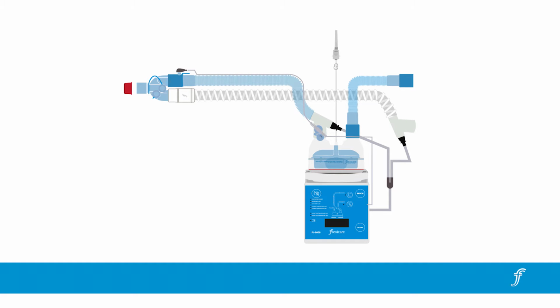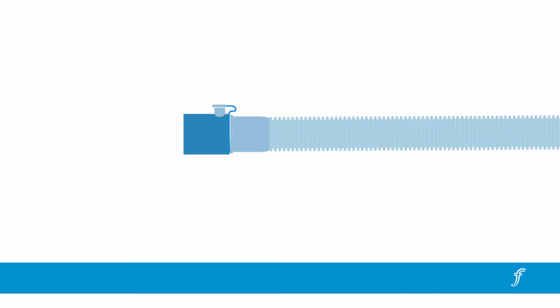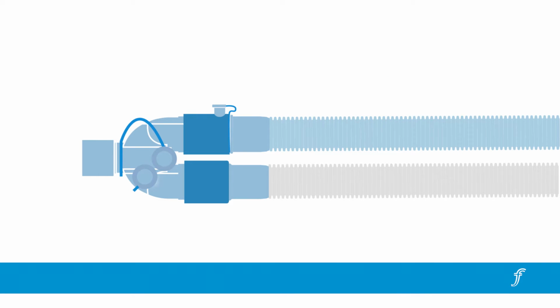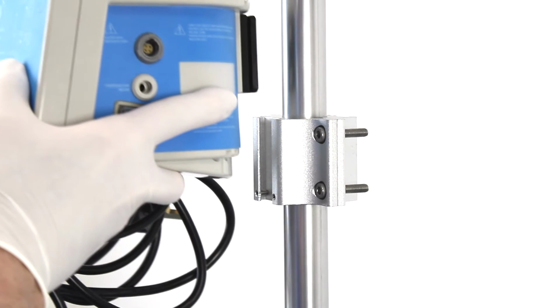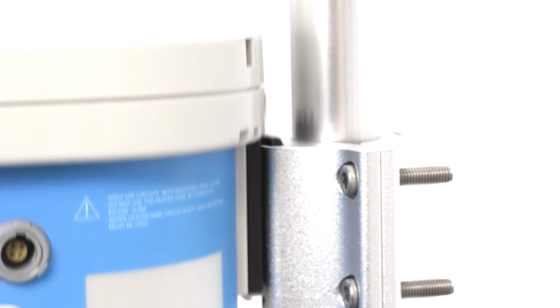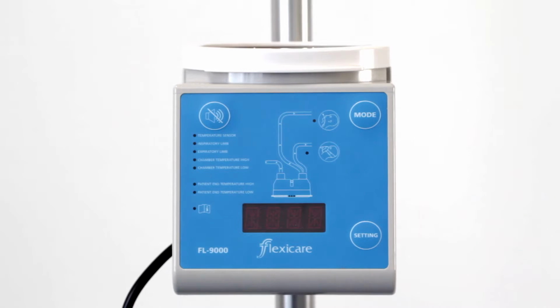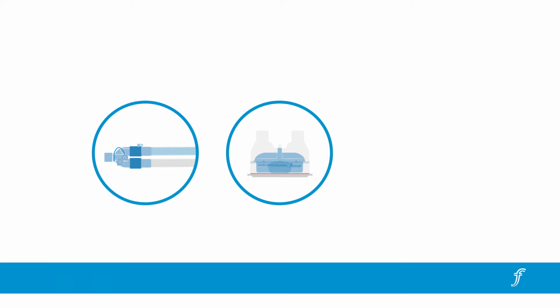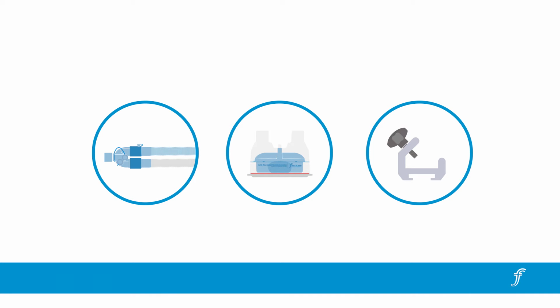The FL9000 can deliver humidified gas using either heated wire or standard non-heated wire circuits and single or dual limb breathing systems. Mount the FL9000, ensuring it is secure and the heater plate is level. It must be positioned lower than the level of the patient's head. The use of breathing circuits, humidification chambers, and other accessories which are not approved by Flexicare may result in suboptimal performance and place the patient at risk.